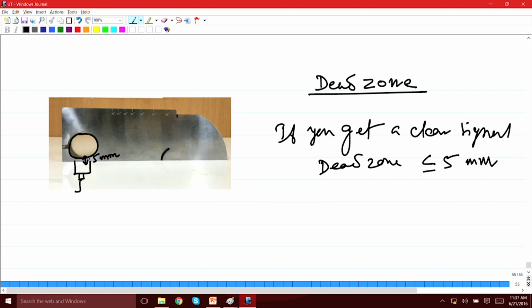So, that will indicate that the dead zone is less than 5 mm. If you do not get a clear signal from this side, then you can put the probe over here, and in this case this particular distance is 10 mm. If you get a signal from the 10 mm distance but not from 5 mm, that will indicate that the dead zone is between 5 mm and 10 mm. On the other hand, if you do not get any signal from the 10 mm distance either, it will indicate that the dead zone is more than 10 mm. So, this is how you can get an idea about the dead zone from this IIW block.